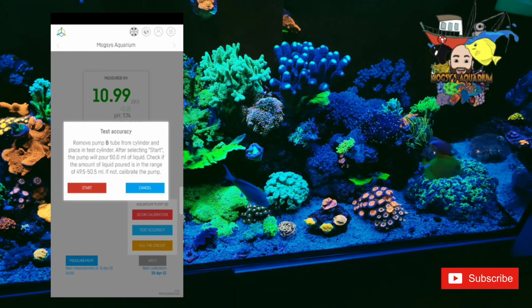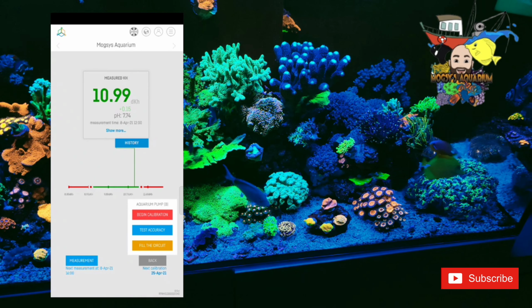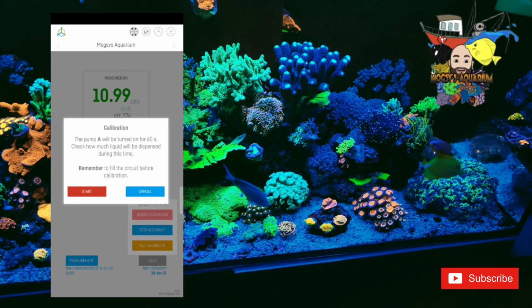You put the larger vial underneath, it doses 50 mils of the salt water into the vial, and this is pretty accurate. Never really had a problem with this one. Same thing applies to the reagent A as well, exactly the same. You begin your calibration, it'll come on for 60 seconds, and then you just have to measure it. You type in how much has been dispensed, so it might be, say, 6.8. You type that in, and then it calculates it over the minute, and that's basically what you do with that.